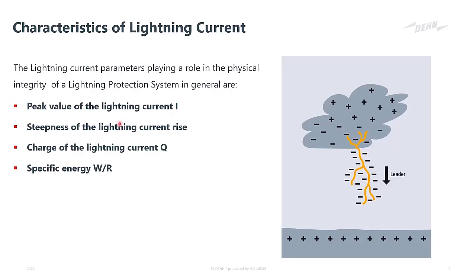So the first one is the peak value of lightning current. The peak value of lightning current is, as it states, the highest amount of current in amps. Now, in lightning protection, we speak about kiloamps only, so it would be the kA value of the lightning strike. Secondly, lightning is an impulse. We'll discuss that in detail as well, but lightning is an impulse, and that impulse has a rate of rise before it reaches its peak value. That steepness and rate of rise also has a mechanical effect on equipment within a lightning protection system. So it will be responsible for mechanical force and flashover and things like that.